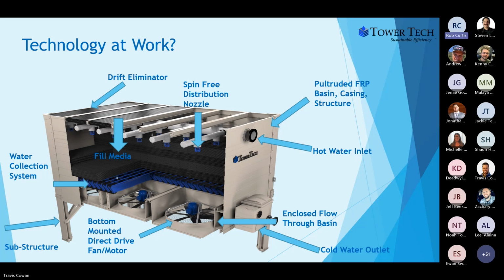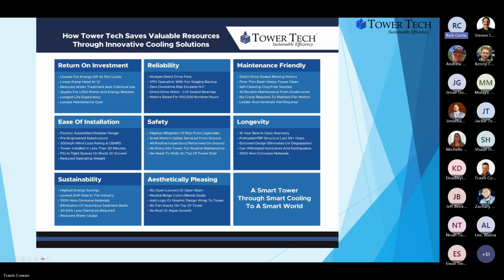So with that, I believe I'll move down to the next slide, which is kind of a recap of a lot of the solutions that we came up with and the benefits. We won't just read them all and go through each and every one of them, but I'll touch on a few as we go through this. And one of the things that's important to me, because I've been talking about this for many years, is being able to provide a reduction in energy for a central plant. When you have a cooling tower that has true variable flow capability, you can impact not just the cooling tower, you can impact the central plant.